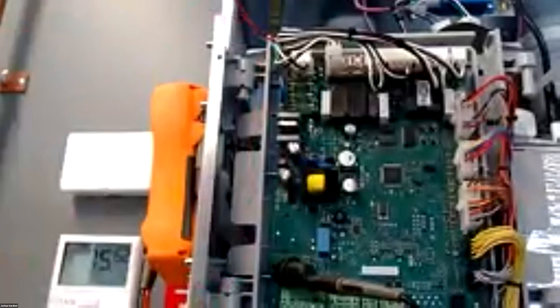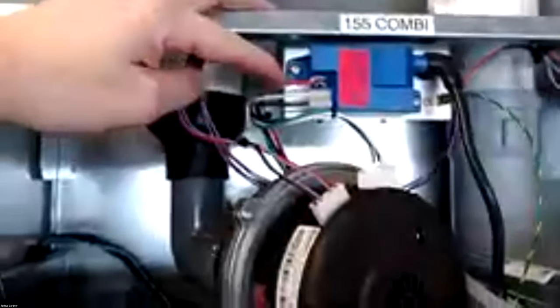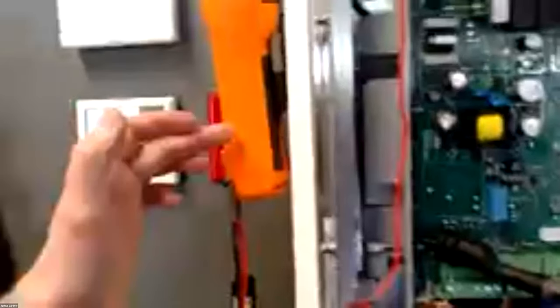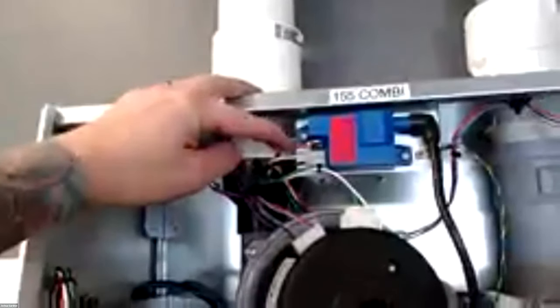So you'll come through one lead. The red wire up here is your flame signal. It just goes down around here, the back, comes around here to pull it, goes through the red lead into the meter, comes out the meter, and into the spade connector. So it completes the circuit. And you're just running your meter in series. It's reading it, but you're not interrupting that signal. So the boiler will still fire and run totally fine. That's how you check your microamp. And if you wanted to, I guess you could pull it up here too and run it in series. It doesn't really matter either way. Here is just a little more convenient because it's right in front of you.